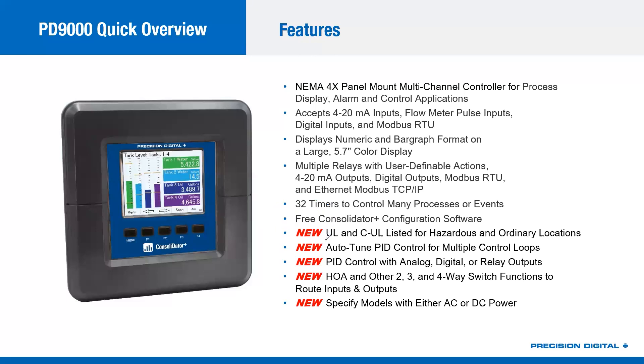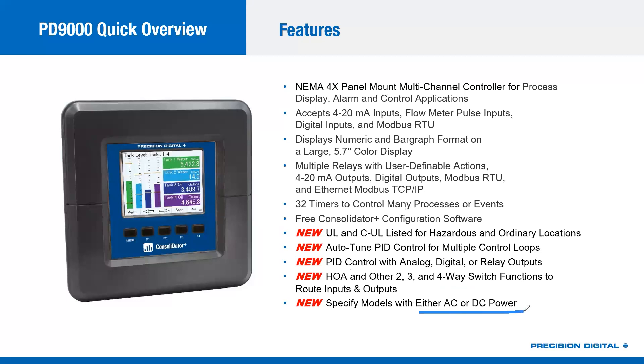Today we're going to talk about the new features specifically: UL and CUL listing for hazardous and ordinary locations, auto-tuning PID control for multiple control loops, and HOA switching support using two-, three-, and four-way internal switching functions. Additionally, you now need to specify AC or DC power when ordering — the part numbers have been adjusted accordingly as a result of obtaining that UL and CUL listing.